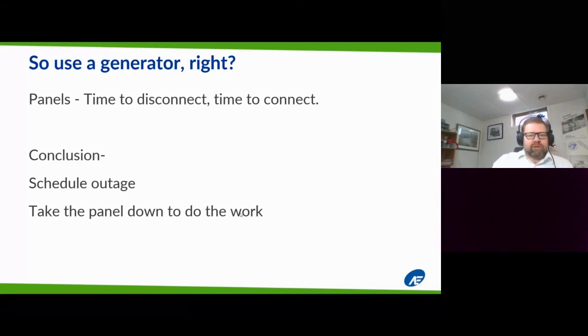If it's a site that usually needs a generator, it takes a lot of time to connect those cables. At the hospital, we connected the cables, did the work, which took about 8 to 12 hours, then disconnected again. We were down 2 to 3 hours just to disconnect and connect the cables at the front and back of that task. So we do need to schedule an outage and take the stuff down. The key is planning and figuring out the correct order to do it in. Sometimes generators are the right choice, sometimes they're not.